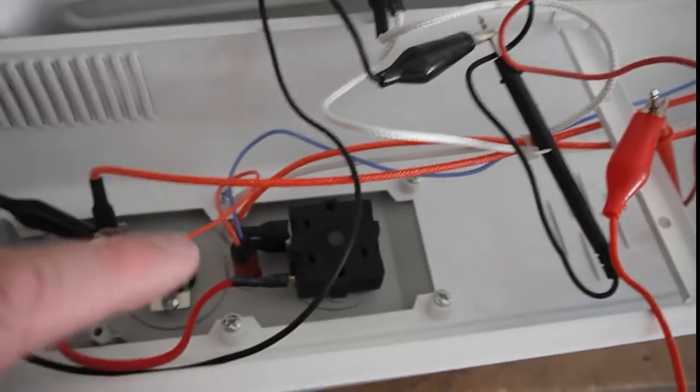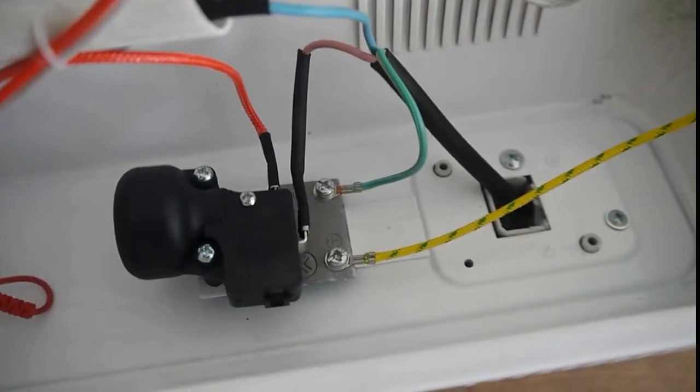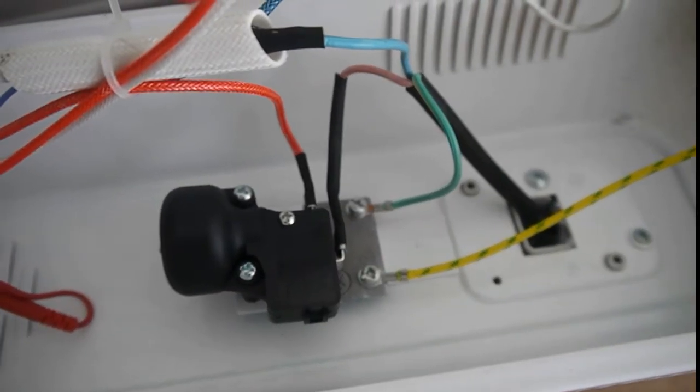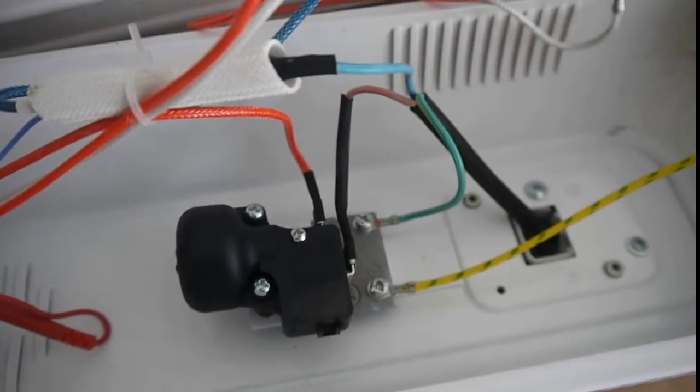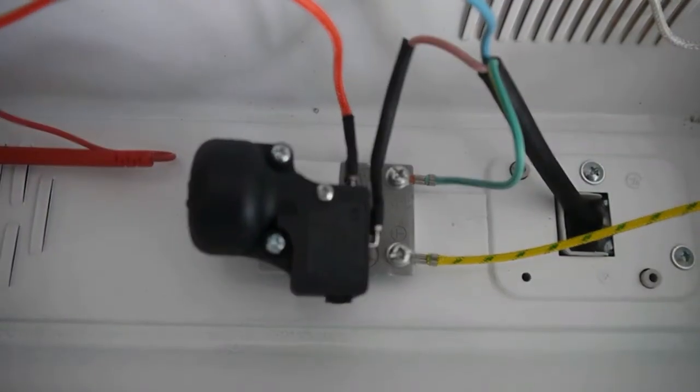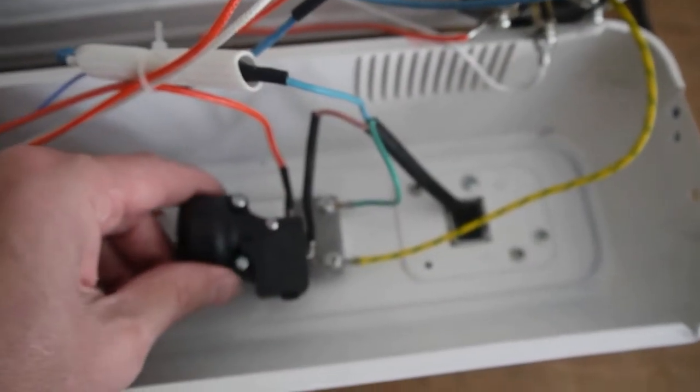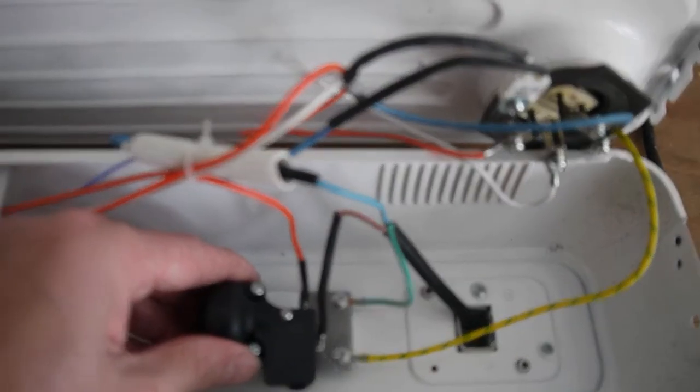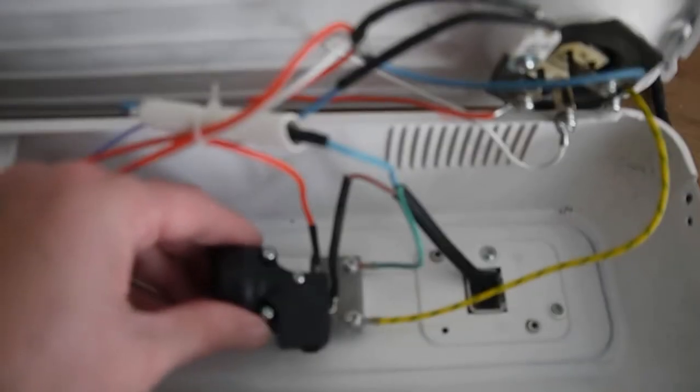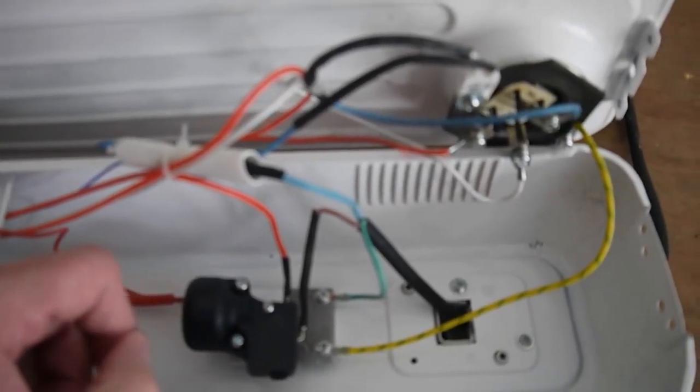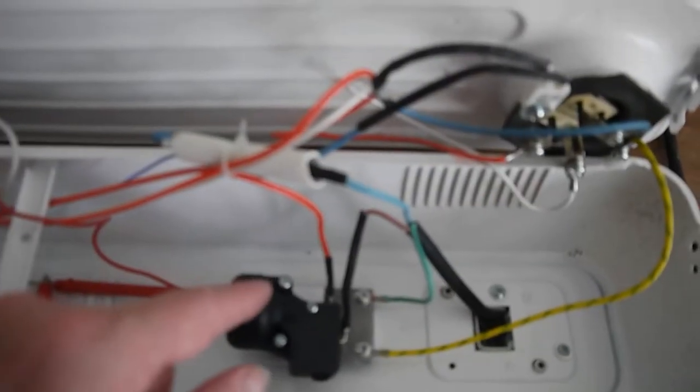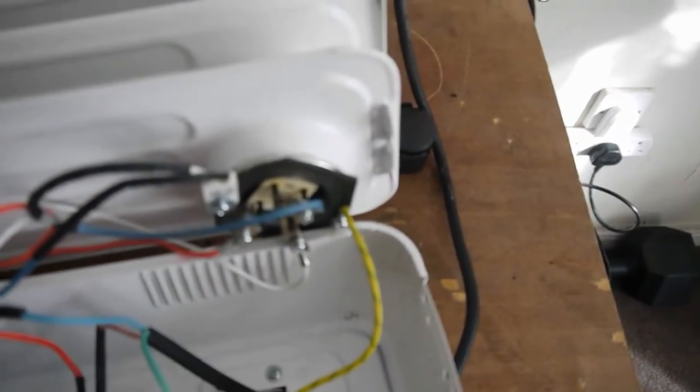This one's more complicated to test, I'll do that last. So I'll check this one here now, make sure there's continuity across it. There might not be because obviously the power's off. So I've just tested that, there's no continuity through it. I'd imagine it's some sort of solenoid or something that needs power going through it for it to function, but anyway I'm skipping that for now and going on to the elements.